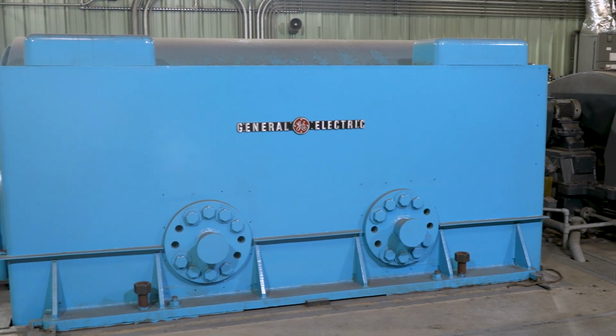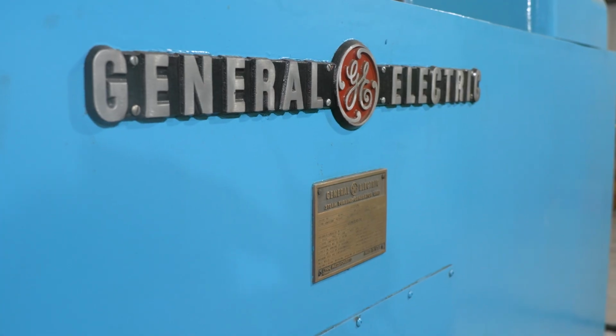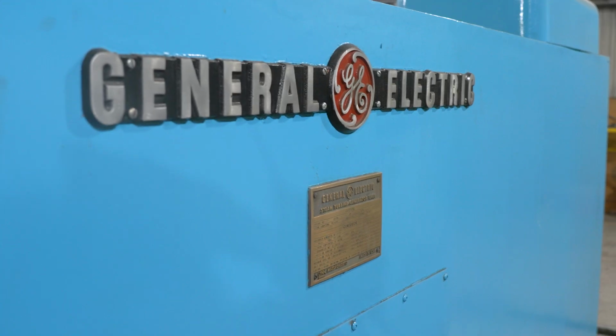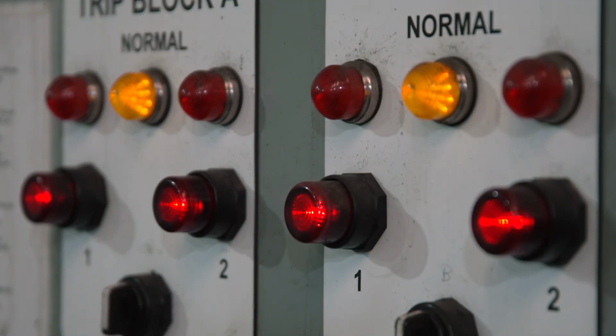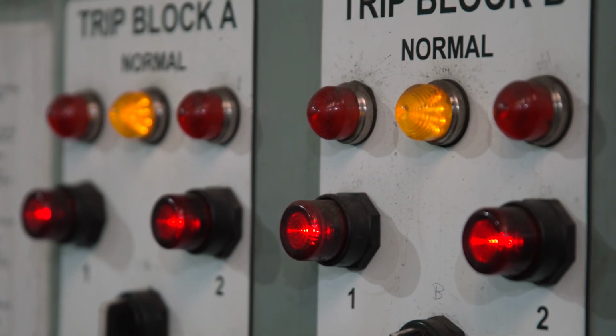Is there any significance to 3,600 being divisible by 60, which is the cycles on the AC? Absolutely. That's a two-pole generator. With a two-pole generator, 3,600 RPM is 60 cycles, and that's what America runs off of.